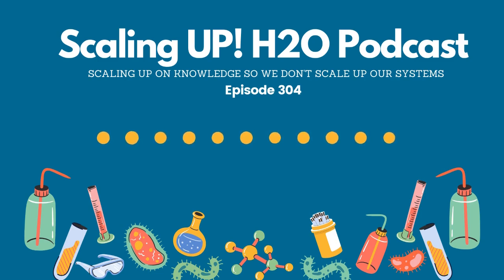Otherwise, you could use a corrosion coupon, and a corrosion coupon is a lot cheaper than that expensive piece of equipment that you are treating. And on a more proactive basis, you can now see what the corrosion rates are within the system, and again, like I said, see if those are acceptable or not acceptable. The great thing about corrosion coupons is they're a shorter interval than whenever that equipment inspection is. So you can make slight adjustments to your program and see if you're increasing or decreasing the effectiveness of the system.